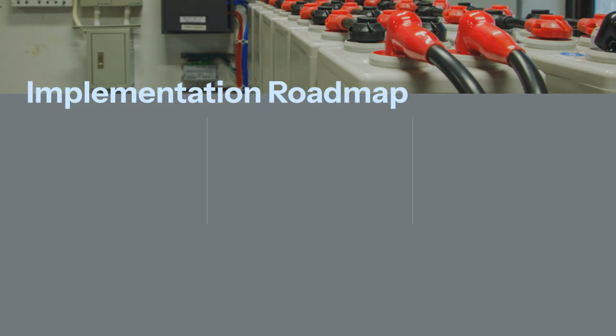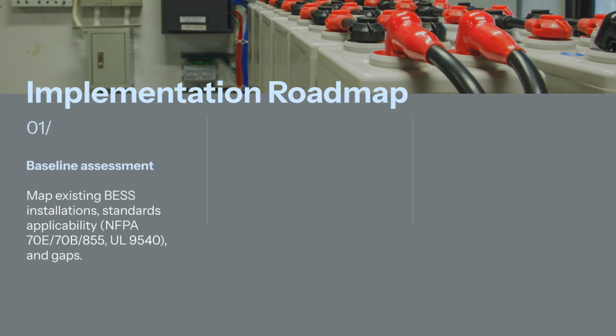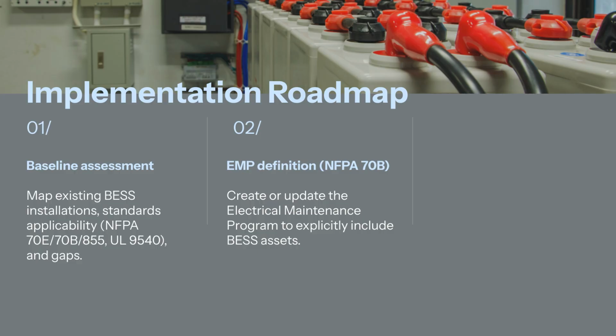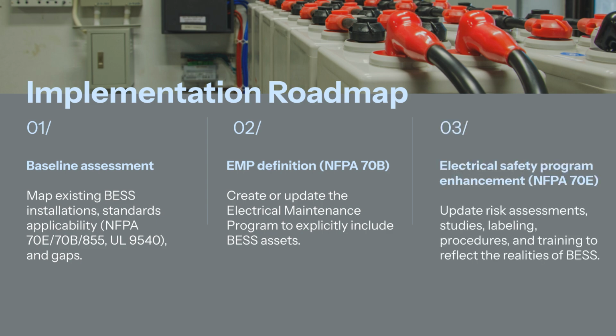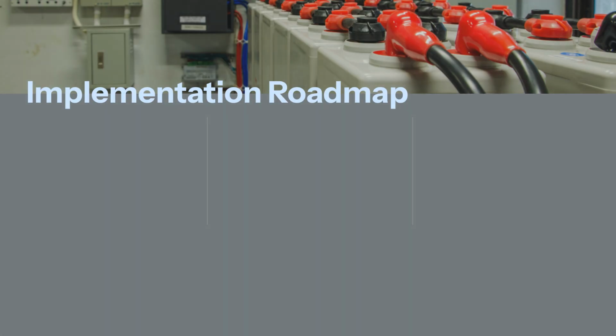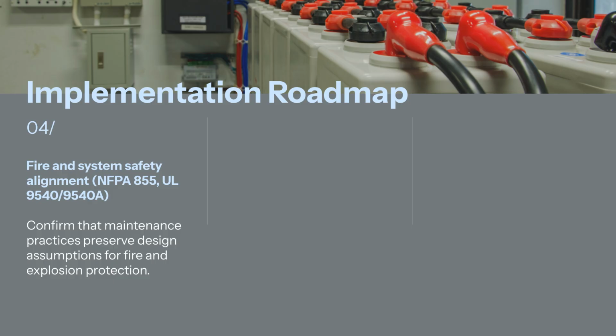Implementation roadmap. Organizations starting up or upgrading a battery energy storage system maintenance and safety program can follow a staged approach. First, conduct a baseline assessment. Map existing battery energy storage system installations, standards applicability, such as NFPA 70E, 70B, and 855, along with UL 9540, and identify any gaps. Second, electrical maintenance program definition, NFPA 70B. Create or update the electrical maintenance program to explicitly include battery energy storage system assets. Third, electrical safety program enhancement in compliance with NFPA 70E. Update risk assessments, studies, labeling, procedures, and training to reflect the realities of battery energy storage systems. Fourth, fire and system safety alignment, NFPA 855 and UL 9540 and 9540A. Confirm that maintenance practices preserve design assumptions for fire and explosion protection.